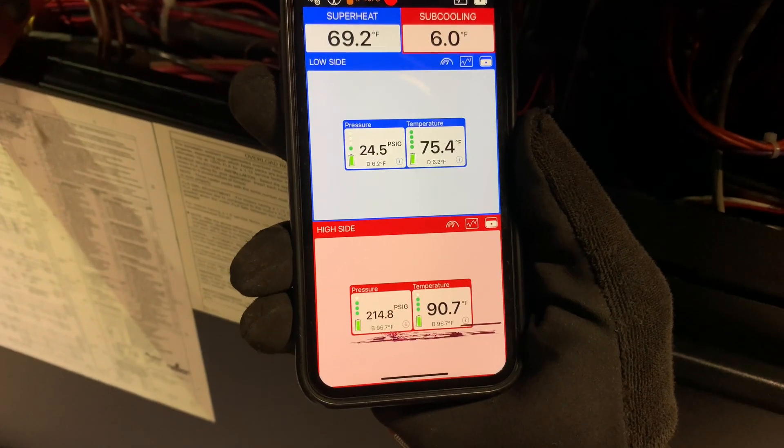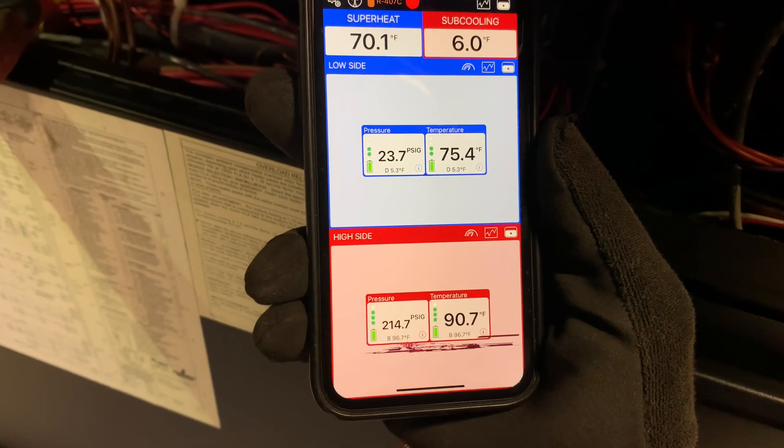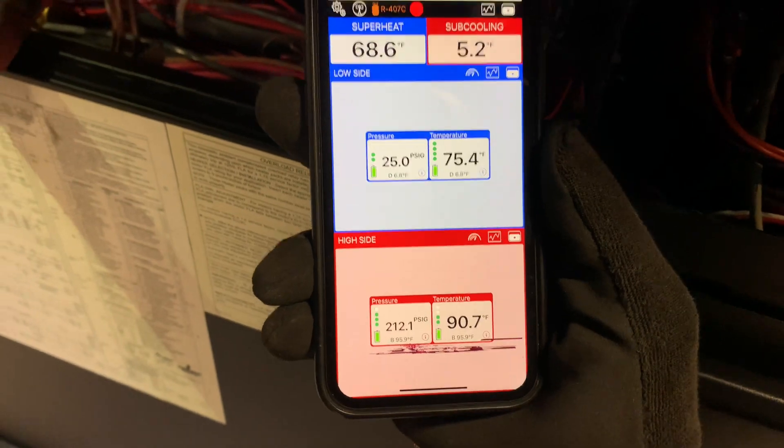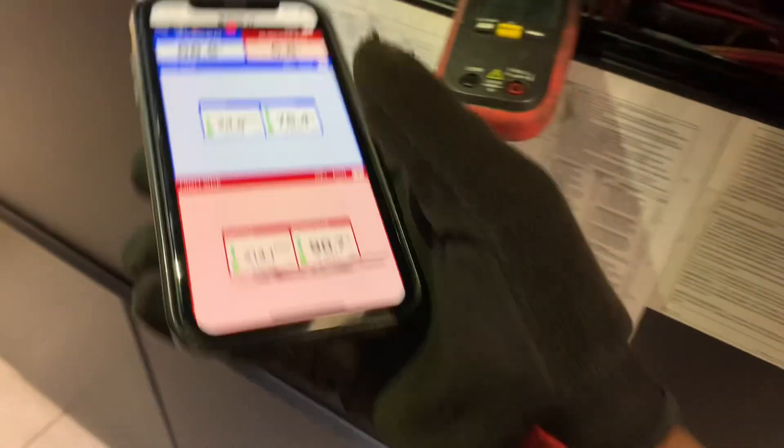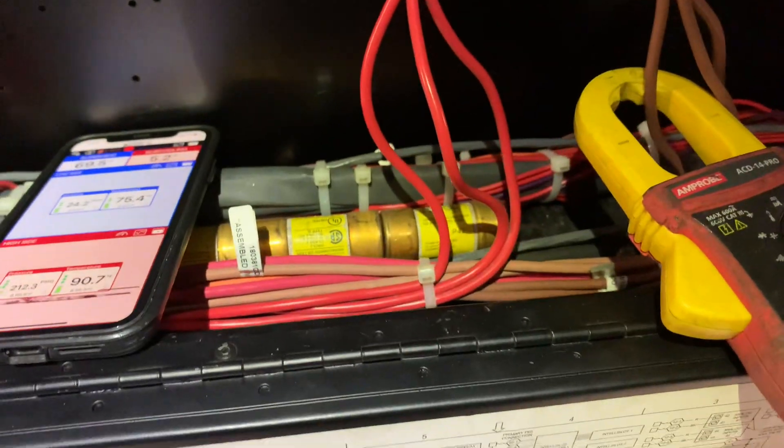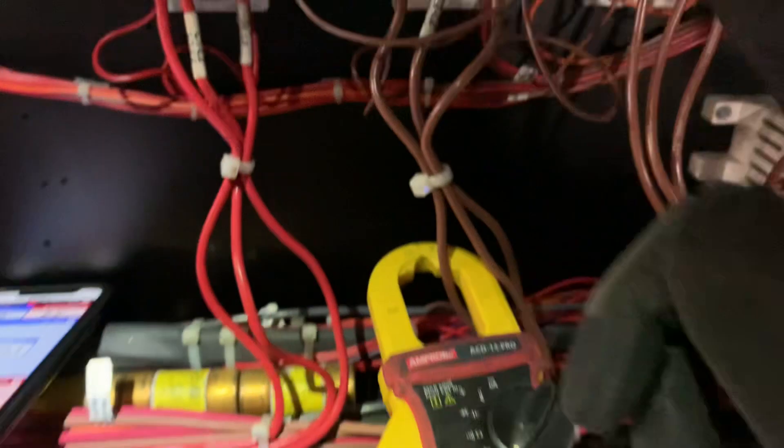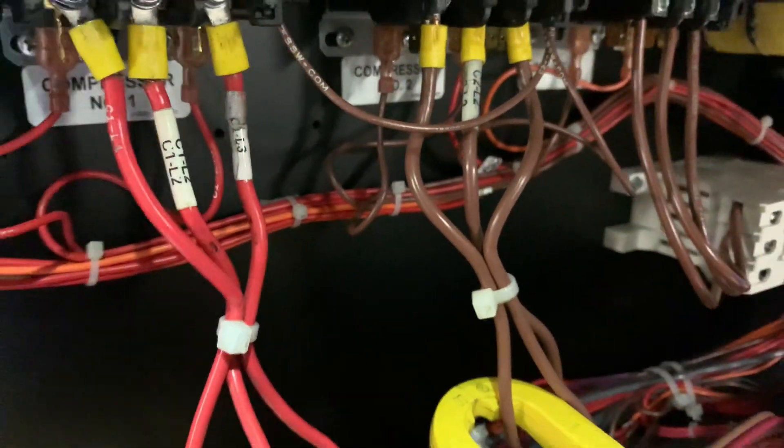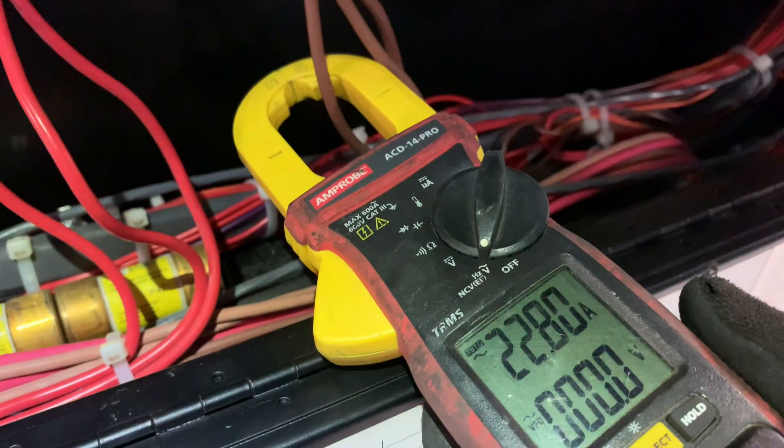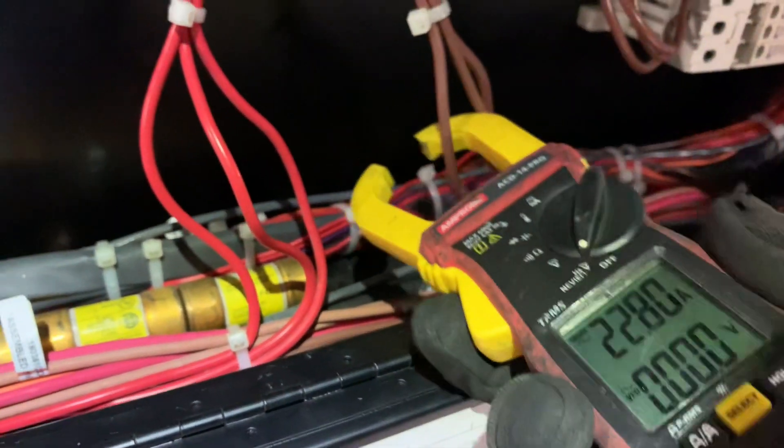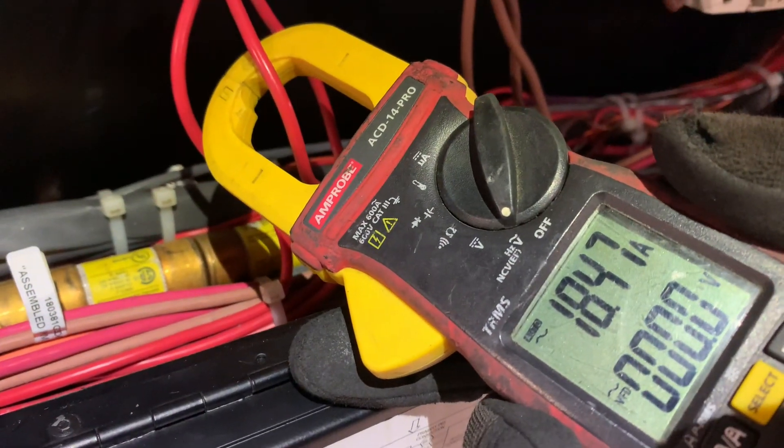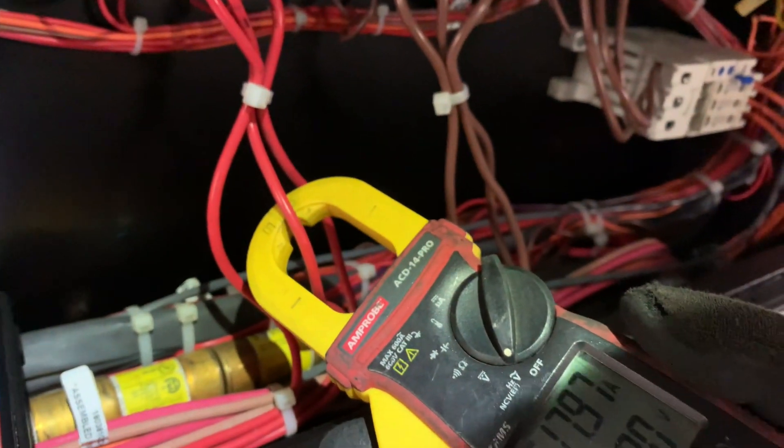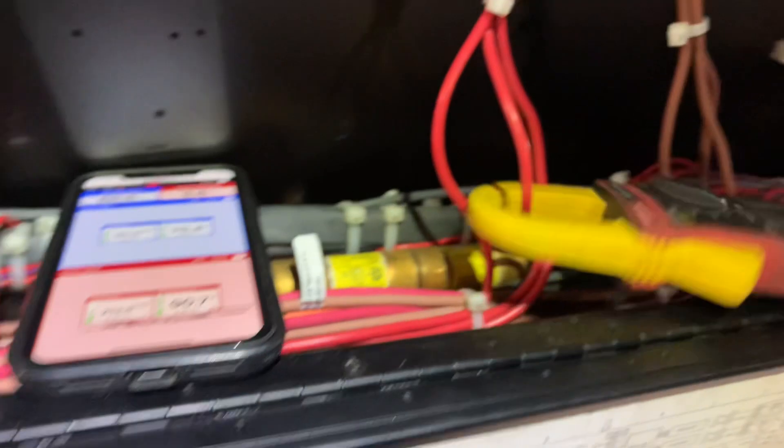This gives me the indication that it's definitely low on refrigerant. In addition to that, I compare the highest amperage draw from the circuit that's good, which is circuit number two. There's no fault from that one or warnings. And that's 22.8 amps. And I go to the highest amperage draw on compressor number one. It's 18. So, a total of about five amps difference. Okay?